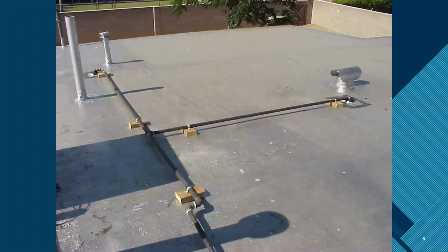And Harris, what's wrong with that fitting? Should we use that for gas, or is it just there to protect the threads? Well, that fitting is there to protect the threads, and that's mainly what it's for. It gives extra support at the edge. Right. So a lot of times when you see new gas, they'll be using that fitting, and it's not tapered as a gas fitting. So you need to make sure there's a hub here. I'm going to point right down here at the bottom. There has to be a hub on the edges of the fittings. So if you're using a coupling or a union and there's no hub on the end of that, it's wrong.